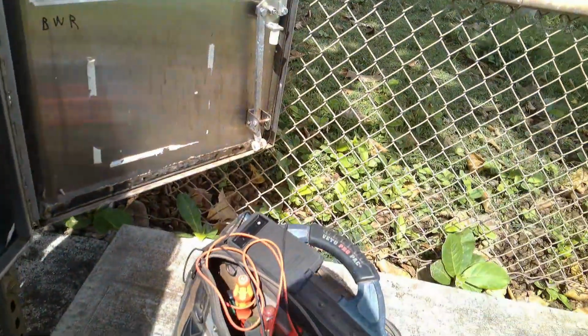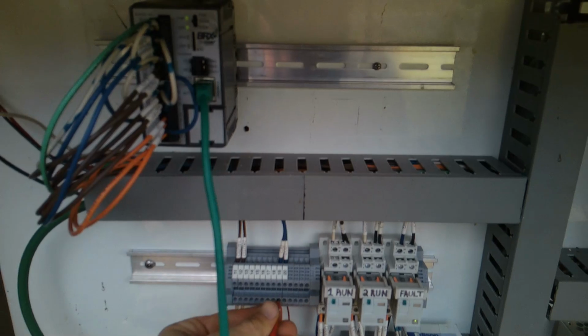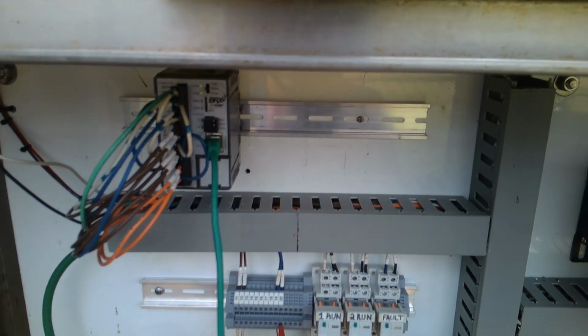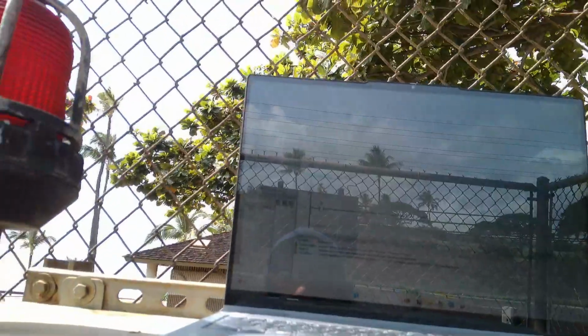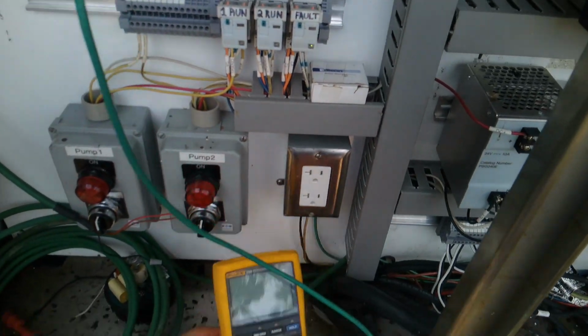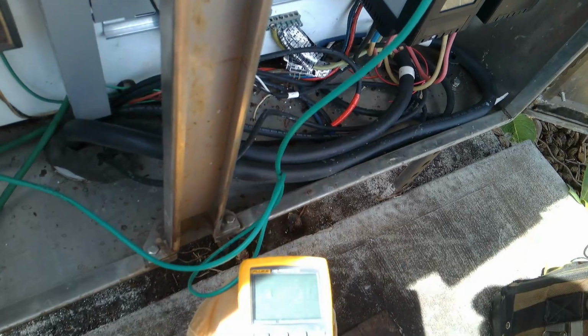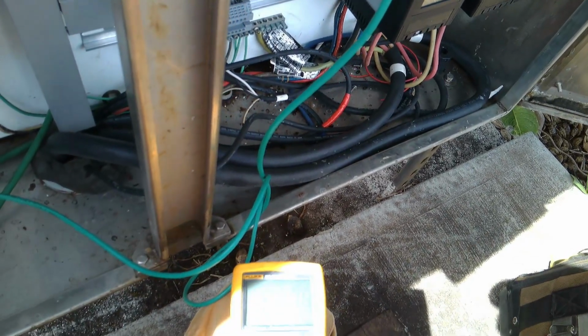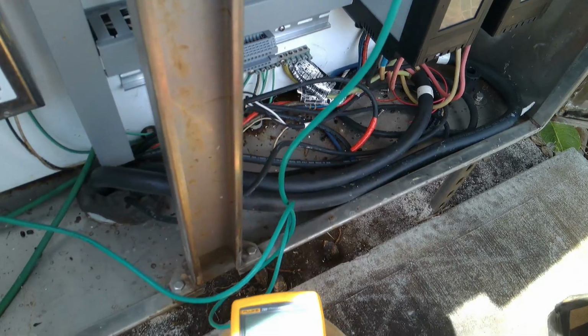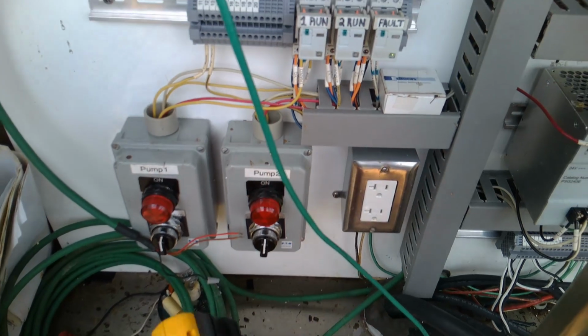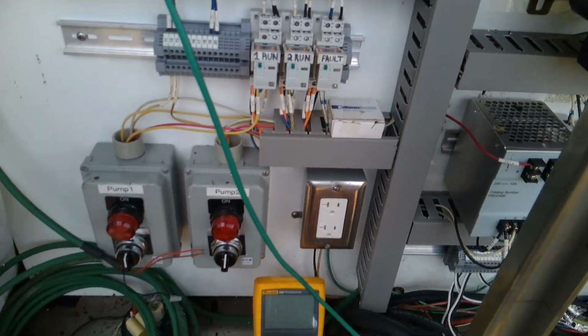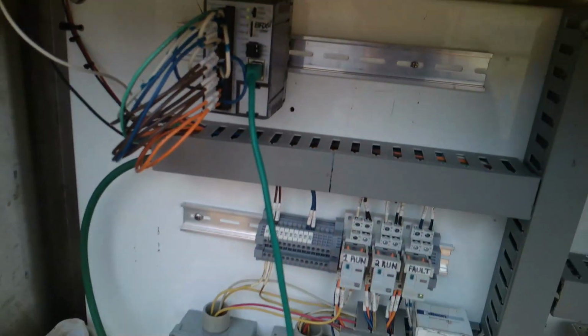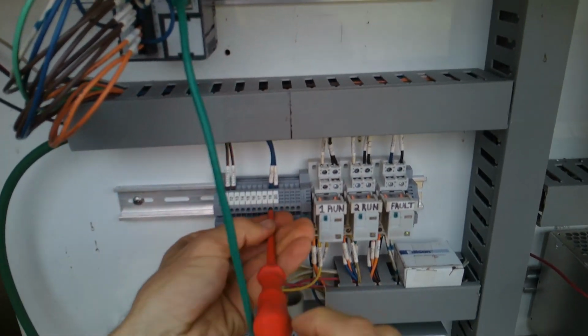So how am I going to do that? I don't really need a jumper wire if I just use these guys. So we'll take our field device off. Good. Then we're going to go into not source mode. We're going to go into simulate mode, where we inject a foreign DC positive, and then this thing becomes a simulated analog device. And we can do that right here with DC2.